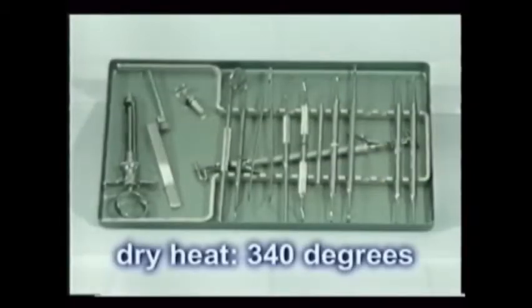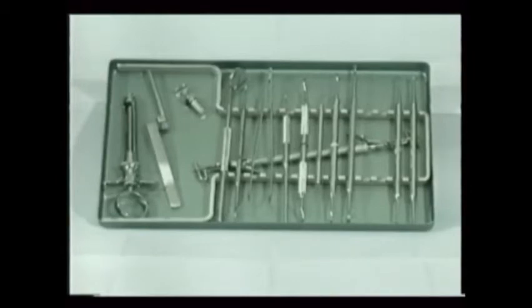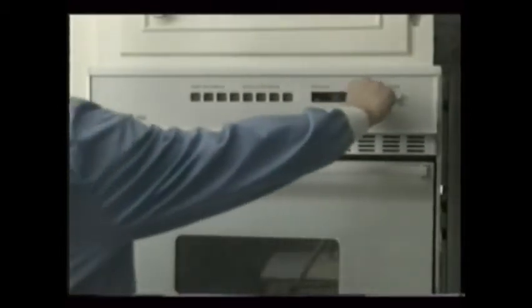Dry heat sterilization is limited to items that can tolerate up to 340 degrees Fahrenheit, and this is usually only metals, although some nylon items can stand the temperature. Most dental offices don't use dry heat, though, in spite of its simplicity, but as a sterilization system, it is simple and effective, albeit somewhat slow.